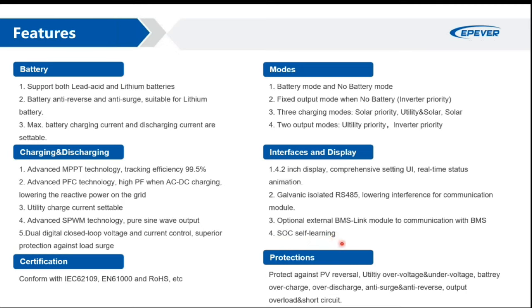SOC is the state of charge of the battery. And this is the first Epever product that measures SOC based on the charging and discharge profile, not only by battery voltage. You are not allowed to discharge the battery when it reaches the LVD, or low voltage disconnect voltage. So the SOC will be 0% at this point. When you hit the LVD, this is recorded as the 0% capacity for the battery. And when you hit the float voltage, which is the voltage at which the charger will stop charging the battery, we can say that it has 100% capacity. So this way you are always calibrating the state of charge.